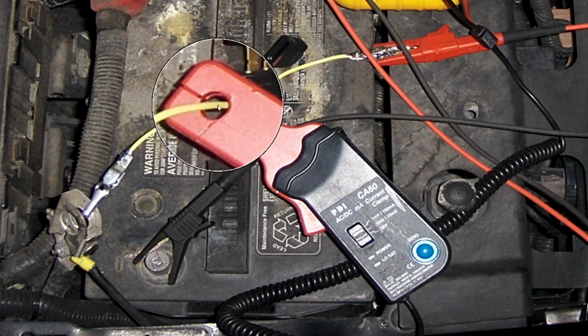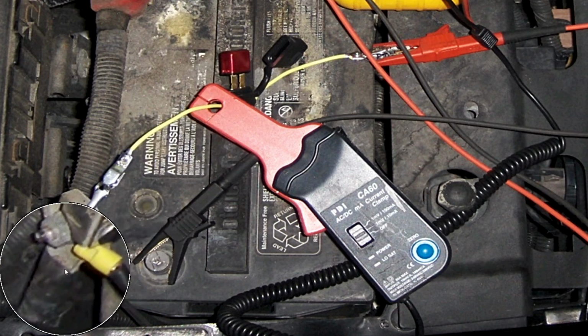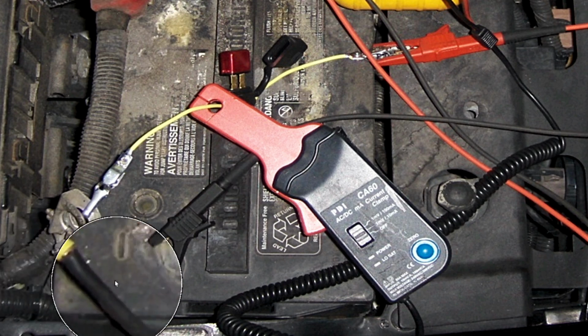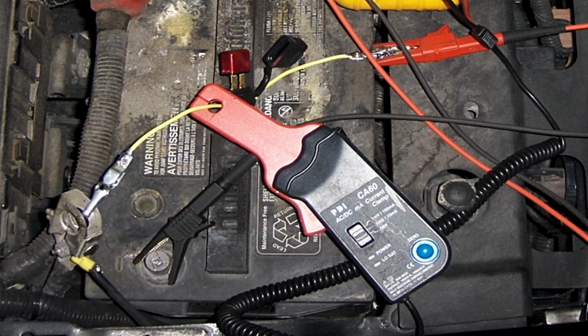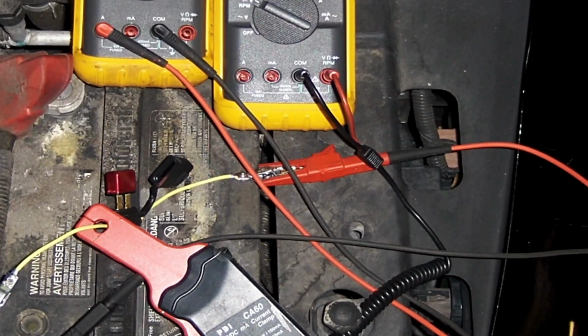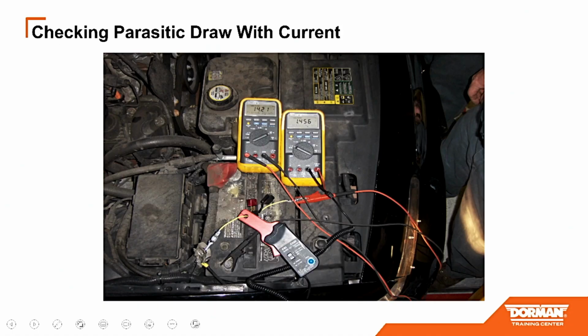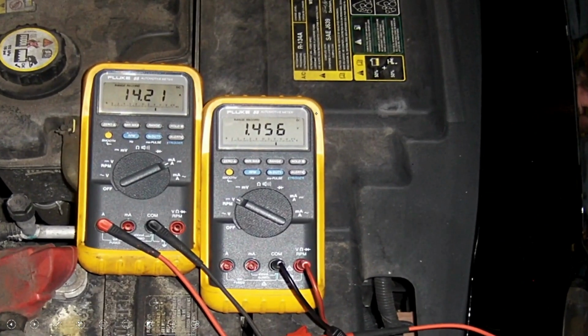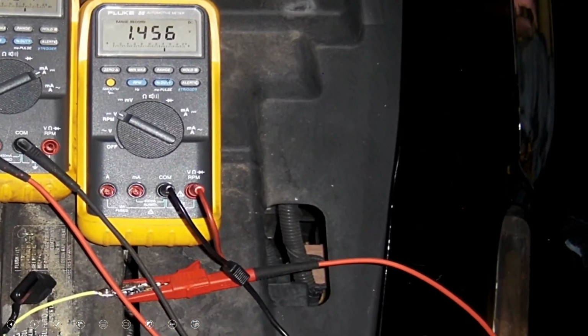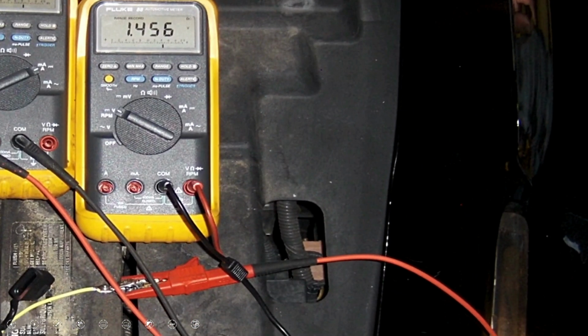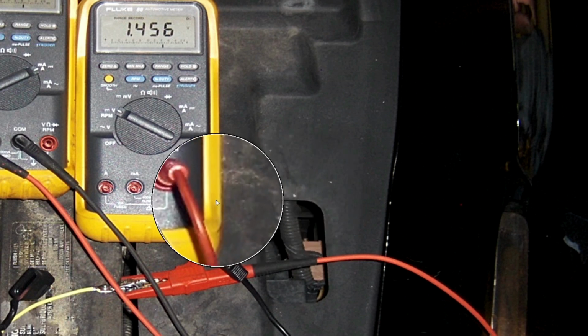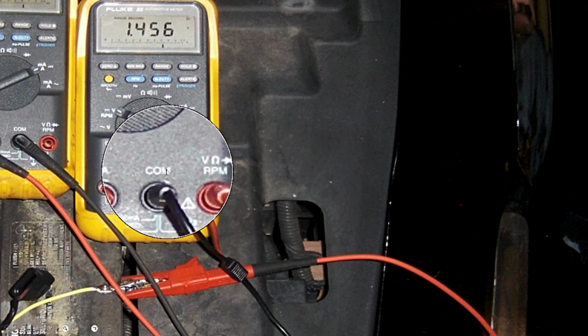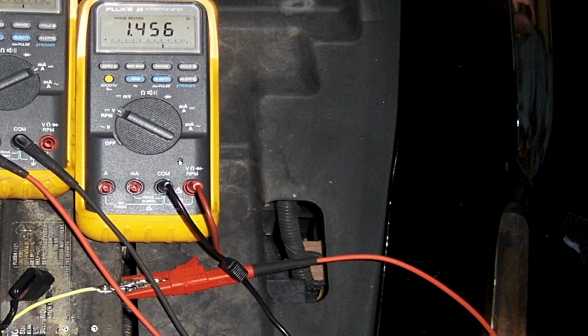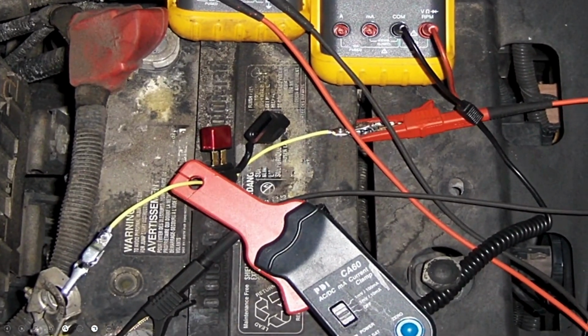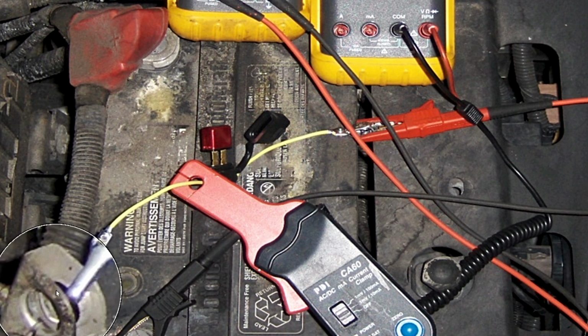This clamp jaw is too small, it's not going to fit around all these wires right here on the negative end, so that's why we're not talking about that just yet. But on that meter, and it's a lot safer, you're going into the voltage jack, the common jack, and then taking that amp clamp. In this case we had to go around a small wire, again because it wouldn't fit there.